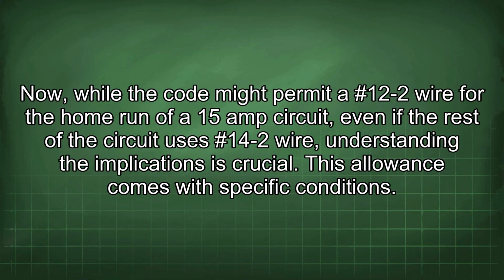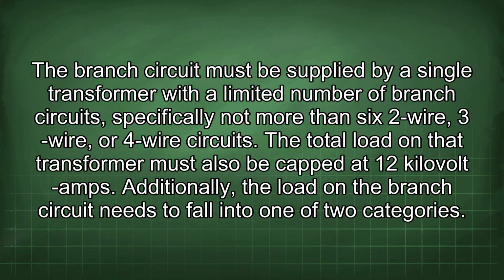Now, while the code might permit a #12-2 wire for the home run of a 15 amp circuit, even if the rest of the circuit uses #14-2 wire, understanding the implications is crucial. This allowance comes with specific conditions. The branch circuit must be supplied by a single transformer with a limited number of branch circuits, specifically not more than 6 2-wire, 3-wire, or 4-wire circuits. The total load on that transformer must also be capped at 12 kVA.